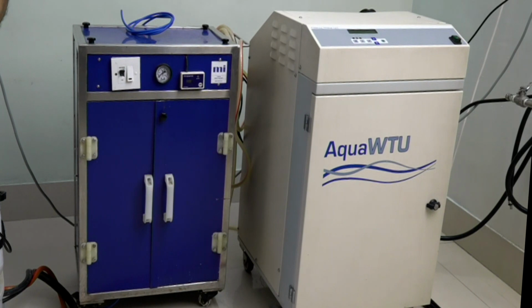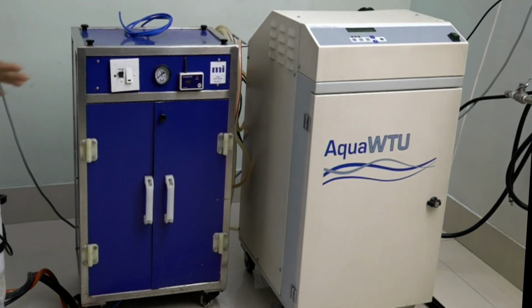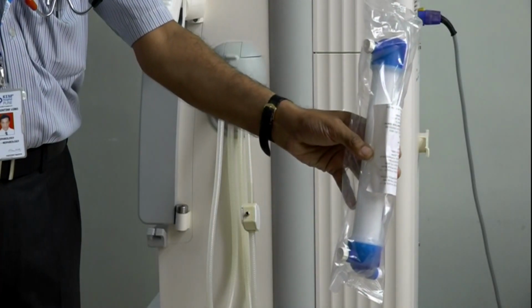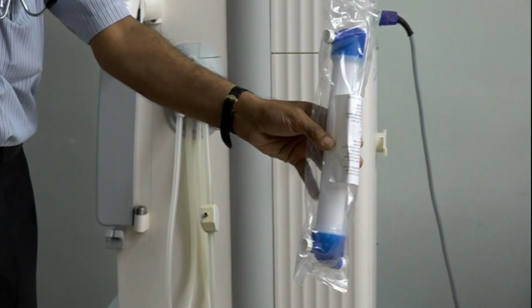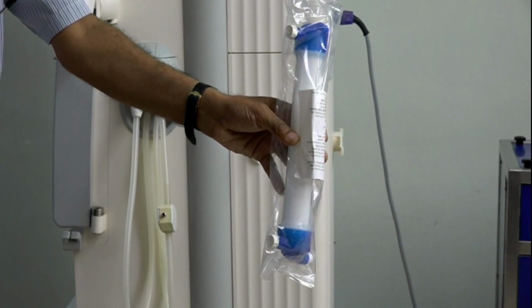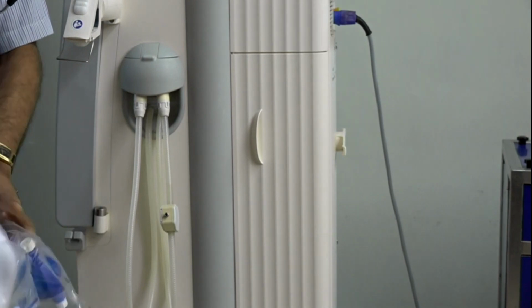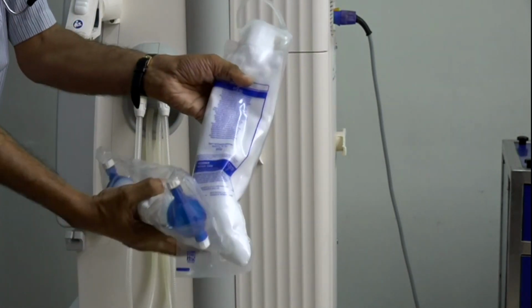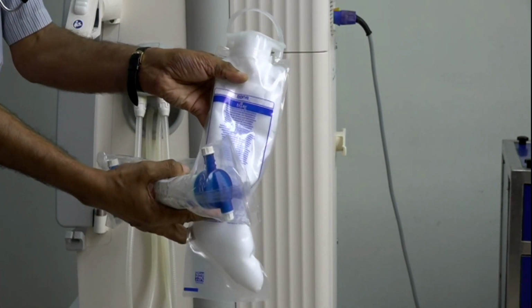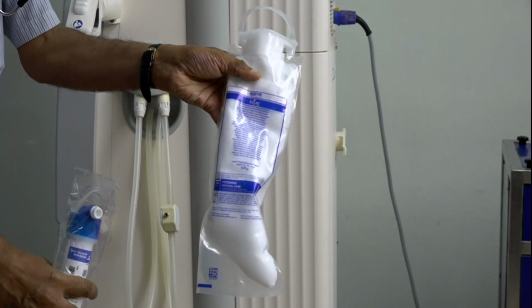However, as this machine is expensive, we built our own machine with the help of a manufacturer from Mumbai. This machine allows us to produce ultra pure water at around 70 liters per hour, sufficient to run 1 to 2 hemodiafiltrations at any given time. We also require the use of a high flux dialyzer and special tubing sets for the 5008 online machine, and the use of sterile bicarbonate, which comes in a powder cartridge form rather than the liquid bicarbonate traditionally used during hemodialysis.